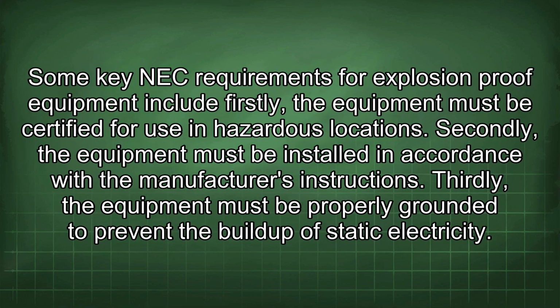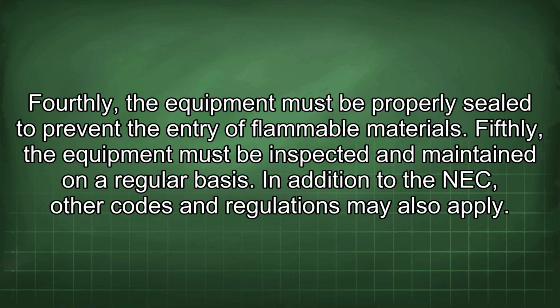Some key NEC requirements for explosion-proof equipment include: firstly, the equipment must be certified for use in hazardous locations. Secondly, the equipment must be installed in accordance with the manufacturer's instructions. Thirdly, the equipment must be properly grounded to prevent the buildup of static electricity. Fourthly, the equipment must be properly sealed to prevent the entry of flammable materials. Fifthly, the equipment must be inspected and maintained on a regular basis.